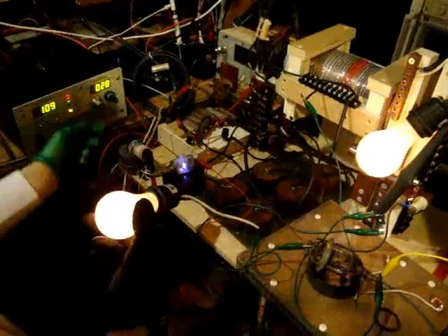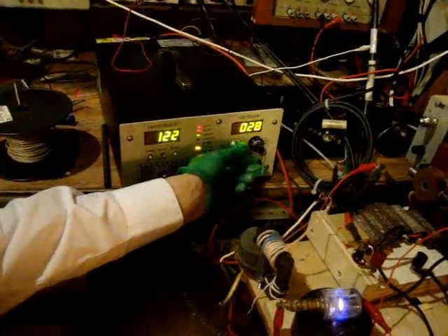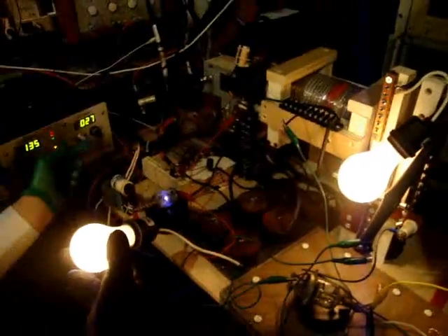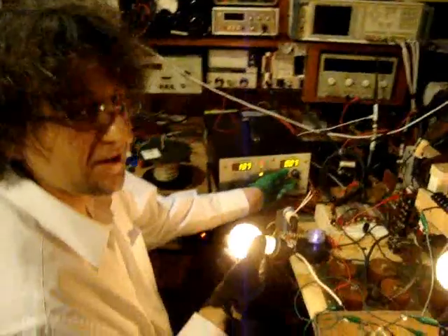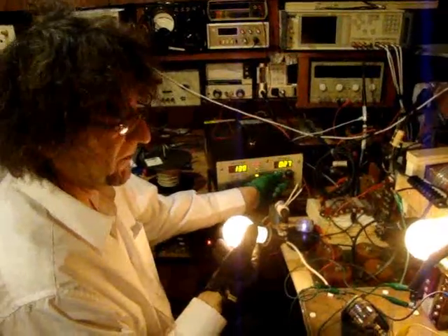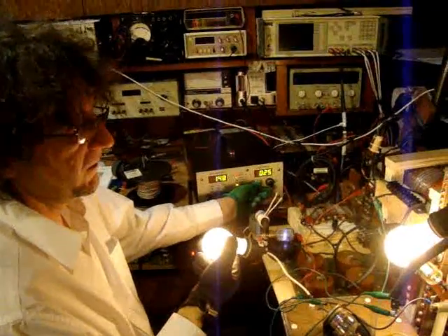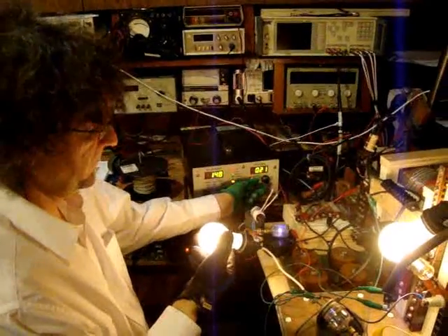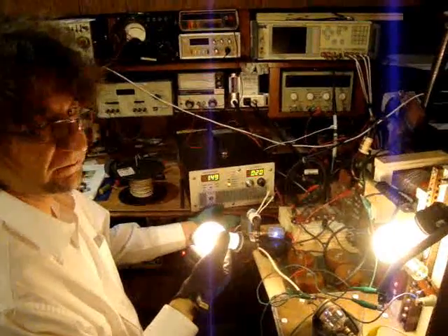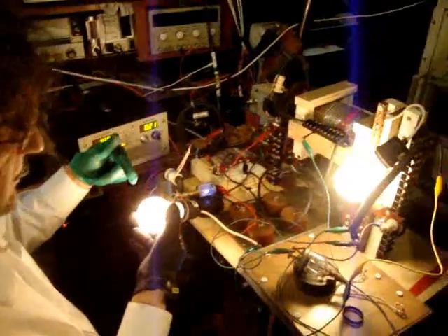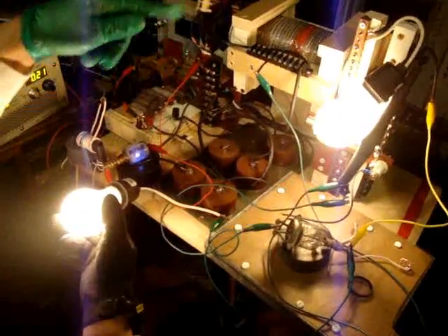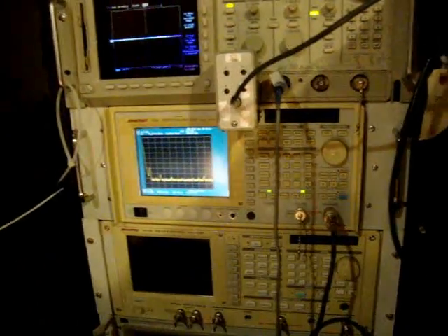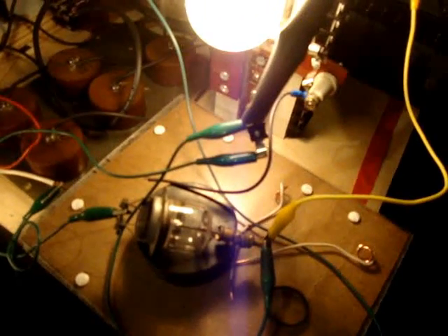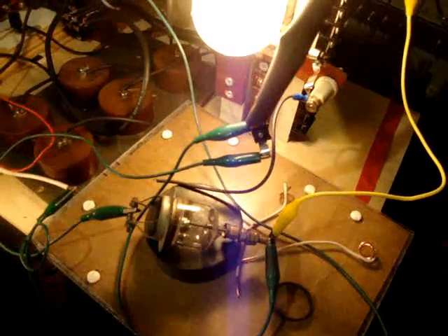I think the problem Wesley was looking at was creating a specific rise and fall time. He has a generator, a Fluke generator, that goes from 0 to 1 kV relatively quickly—I'm not sure of the exact specs of the amplifier that moves the waveform up and down. He tried loading other transformers on the output, but because of poor coupling or air gaps, he wasn't able to couple the energy and get the step-up he wanted. So I designed a transformer with extremely low leakage inductance, a ratio of 10 to 1, and very high efficiency—a voltage coupling coefficient better than 99%, about 99.8, almost 99.9% voltage coupling.